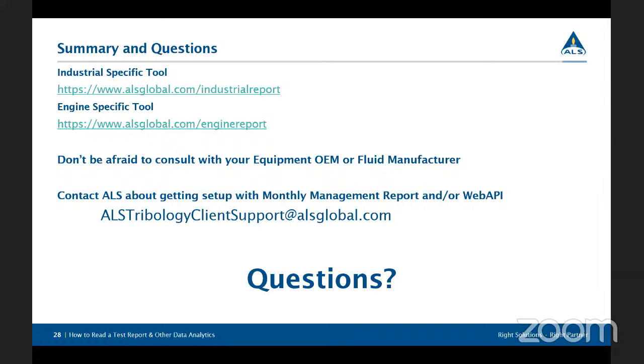So that's a good thing to consider: if you get back a normal report, but you know that there's maybe a lot of hours on that oil, that's a good sign. That means at least everything's okay. If it was a really short interval and the wear levels were higher, that's where you'd want to be concerned and call the lab and say there's a really short amount of time on this fluid, even though the wear levels you say are normal, would it still be normal based on a short amount of time?